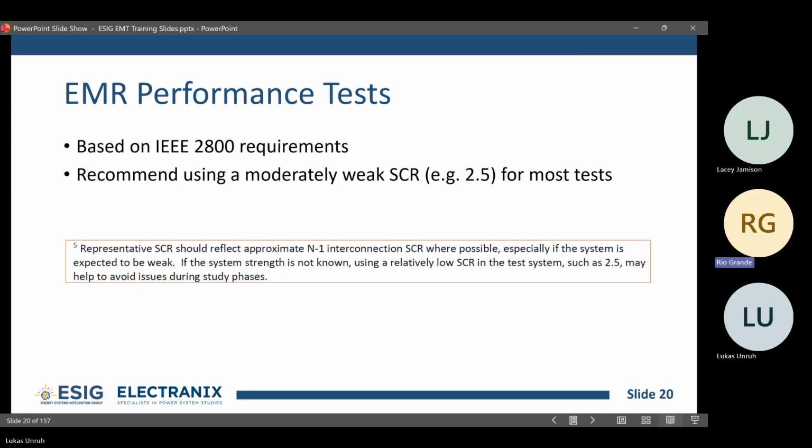If you have a real test, not for this, because there's probably design evaluations before you have a connection, but if you have a real test with real data, like a mod 26 reactive power test, you can use that test to calculate your X over R ratio and grid impedance as well, right? Because you can just take the magnitude of the Q response and the magnitude of the voltage deviation, and that gives you X over R and impedance. Like I said, you can do the same thing in a load flow as well. But doing the real test is also really useful for those who are going to do this again post commissioning.